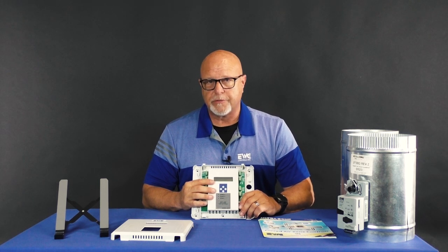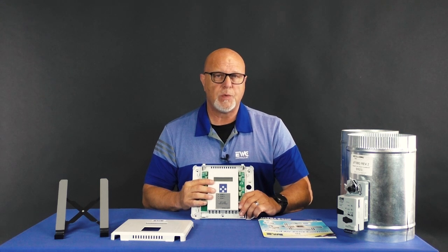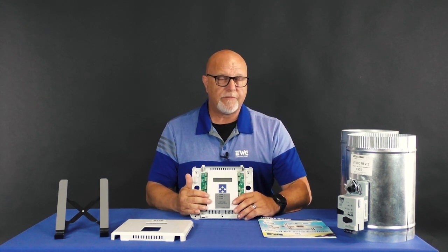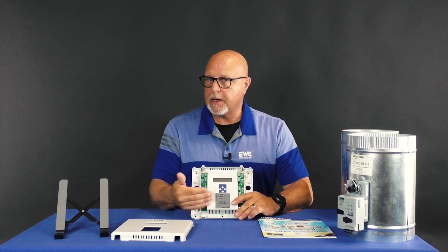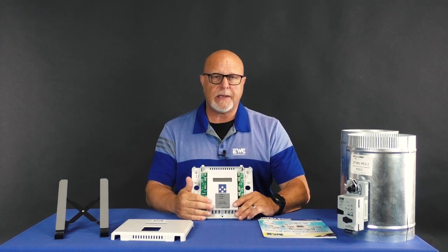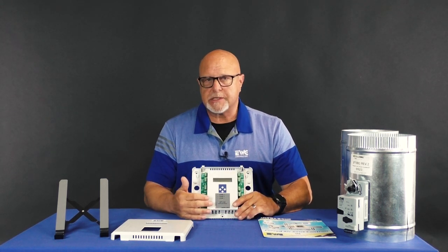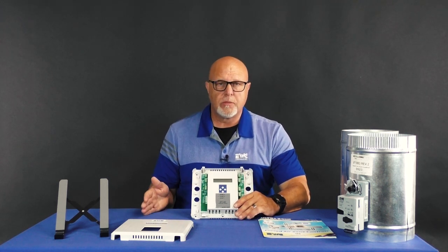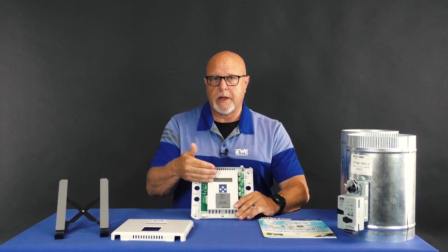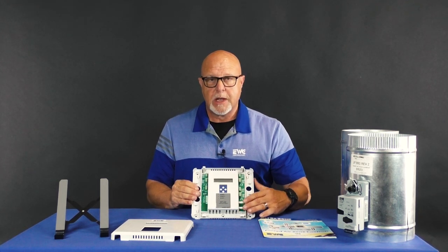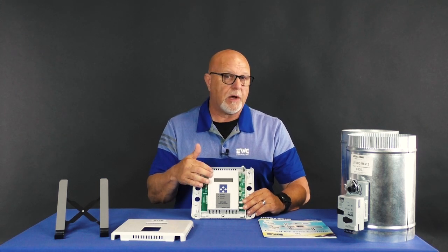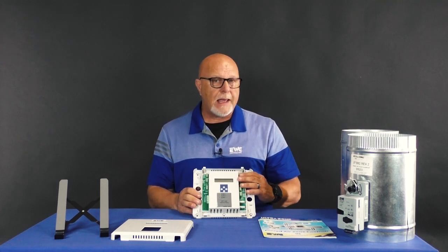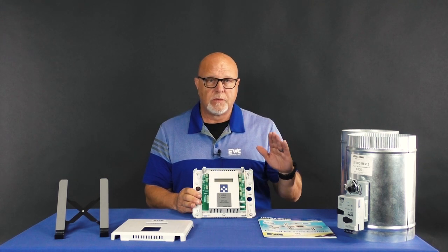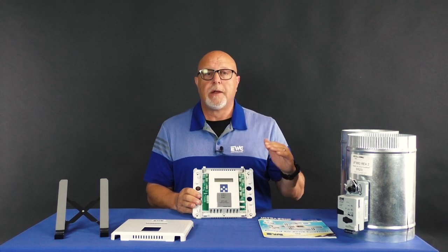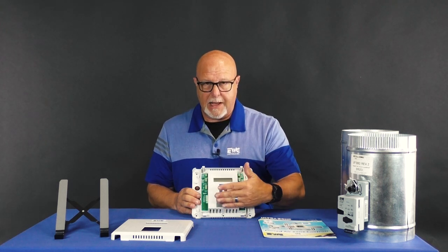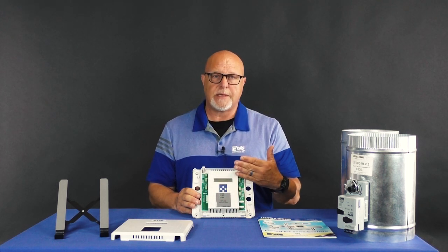The very most crucial feature of the setup would be the static pressure that you want this system to operate at. It comes from us set at a 0.5 inch static pressure. You can change that, or you can allow this board to discover the static pressure through its commissioning setup. If you choose to just leave it at the 0.5, then when zones are calling or not calling, and the pitot tubes that you install into the supply and the return measure that static pressure, and it increases or goes above the static pressure that you have set, this board will automatically open the zones that are not calling, or the zones that you have told it to open, toward the open position, thereby keeping that static pressure below the set point that you have set in this board.